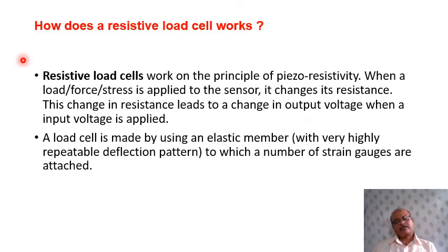In the previous slides we have explained the strain gauge. We will explain this strain gauge with some animation so that you can understand better and more knowledge is added to your study. So how does a resistive load cell work? A resistive load cell works on the principle of piezoresistivity. When a load or force or stress is applied to the sensor, it changes its resistance. This change in resistance leads to a change in output voltage when input voltage is applied.